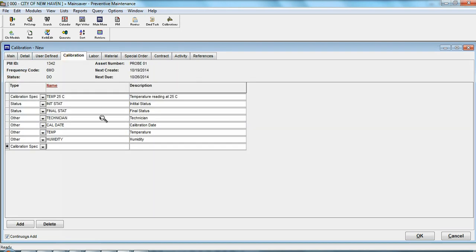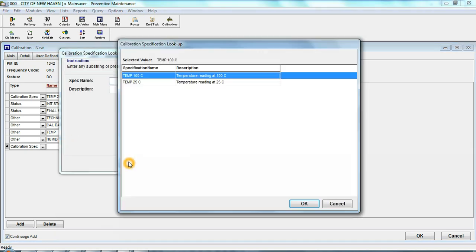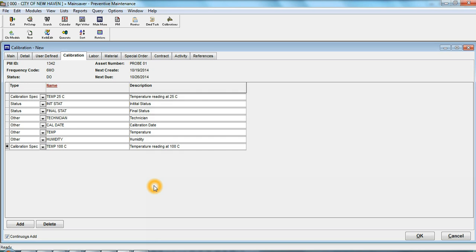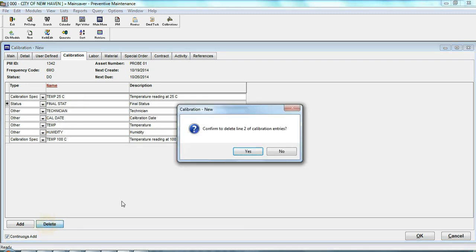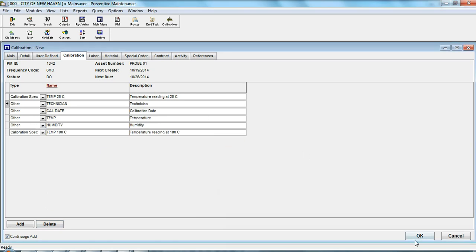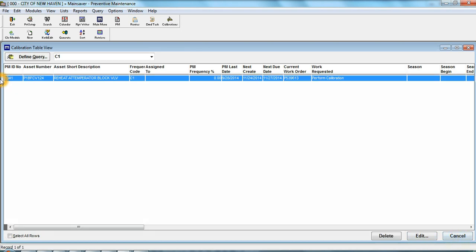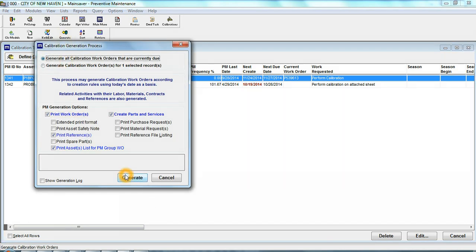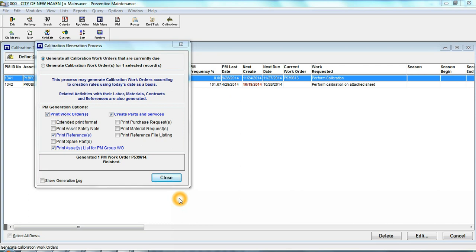On this tab for the calibration now, it already has my temp at 25C specification in there because that was attached to the asset. I also want to add in the 100C, so those will be on the sheet. Some of these things are just fields you can record about the ambient temperature, humidity, that type of thing. If you don't want these, you can delete them out. There's no harm in getting rid of these. And that's all I need to do. So whenever I'm ready to generate, I come in and we'll just go ahead and click generate and generate all calibrations currently due. And it will print out the work order and it will print out the calibration sheet.